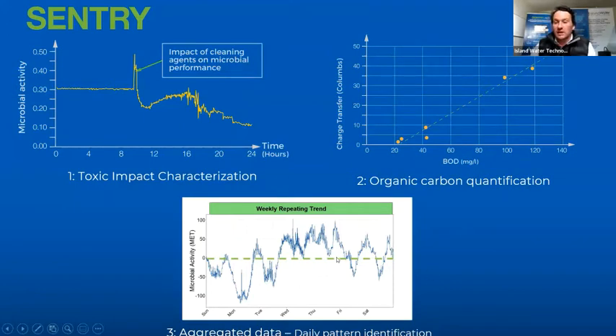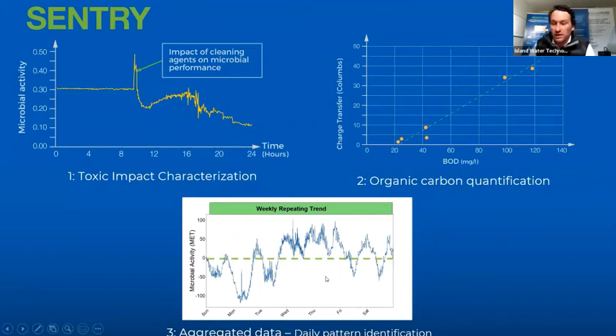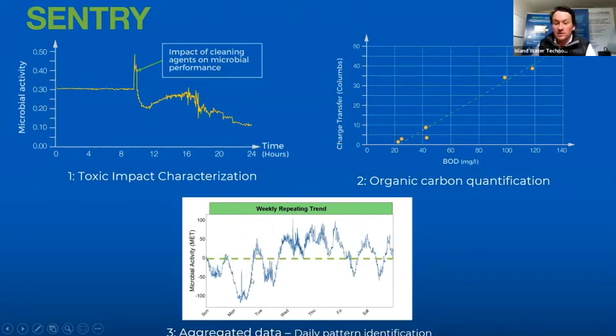The third thing we do: because the sensors are biofilm-based and thrive in wastewater — and we don't want you physically cleaning the sensor surfaces — we can place them in wastewater streams and extract really valuable insight over extended time periods. For example, this is a weekly repeating trend from a primary clarifier of a municipal plant with industrial activity in the collection system. The operator can clearly see on average what's happening, pay attention to Wednesdays through Fridays when the big load comes in, see the diurnal patterns, and identify optimization opportunities during times of lower microbial activity.